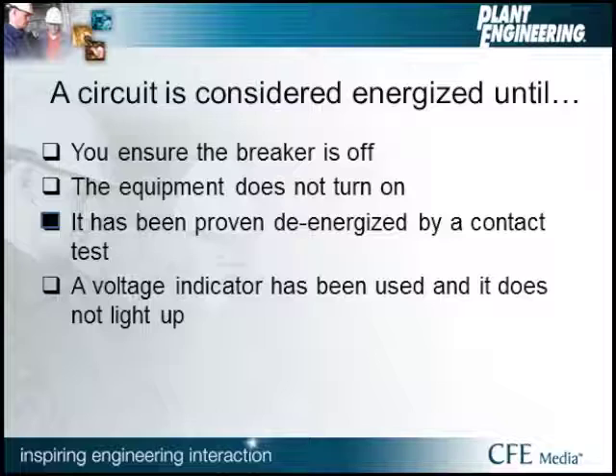So a circuit is considered energized until you've proven it's de-energized by a contact test. You cannot use a voltage indicator for this. It will not guarantee zero voltage.